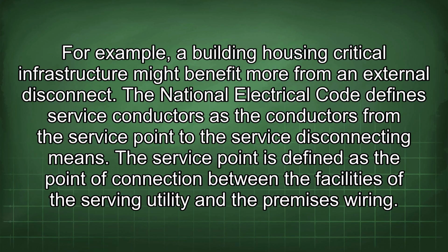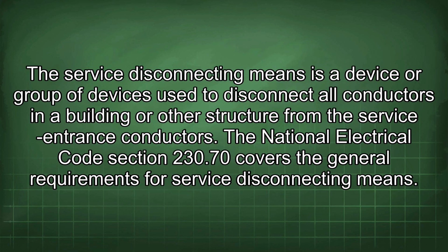The National Electrical Code defines service conductors as the conductors from the service point to the service disconnecting means. The service point is defined as the point of connection between the facilities of the serving utility and the premises wiring. The service disconnecting means is a device or group of devices used to disconnect all conductors in a building or other structure from the service entrance conductors.